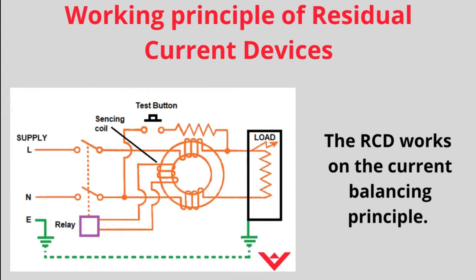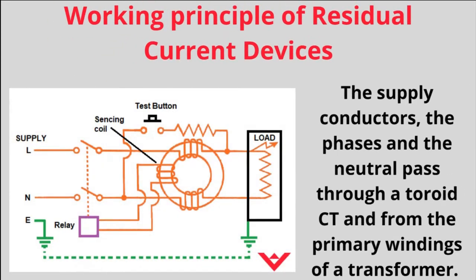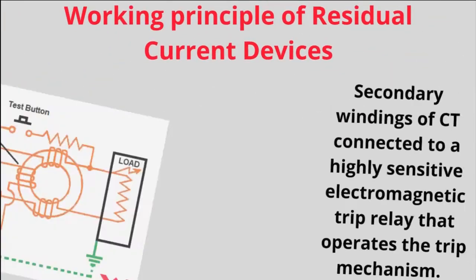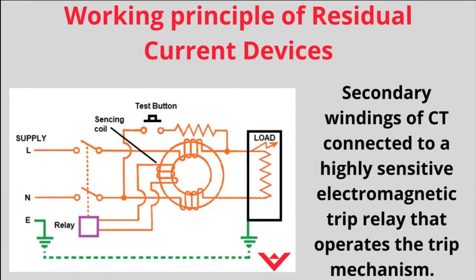Working principle of residual current devices. The RCD works on the current balancing principle. The supply conductors, the phases and the neutral, pass through a toroidal CT and form the primary windings of a transformer. The secondary windings of the CT are connected to a highly sensitive electromagnetic trip relay that operates the trip mechanism.